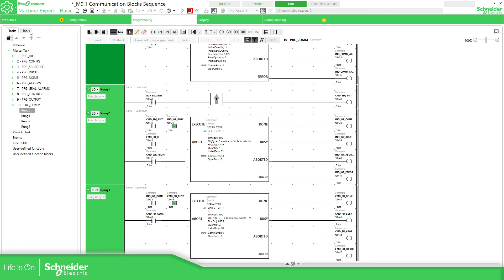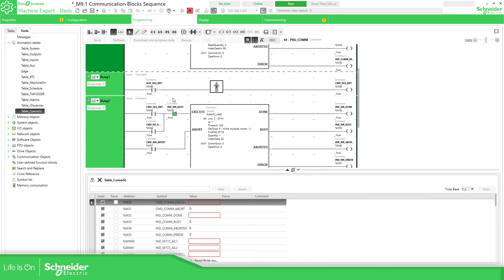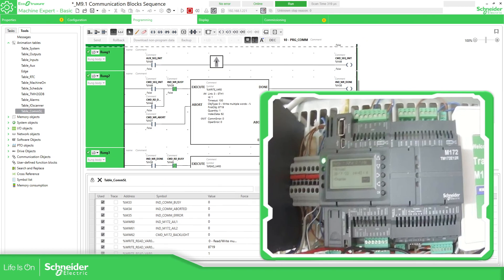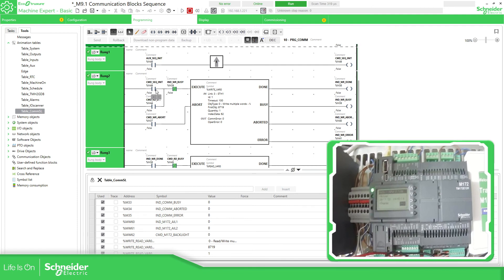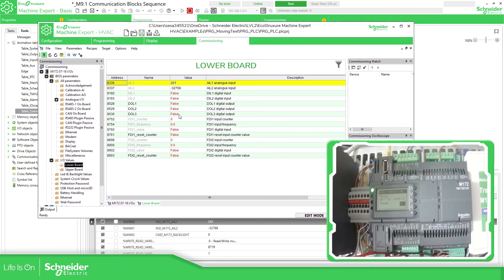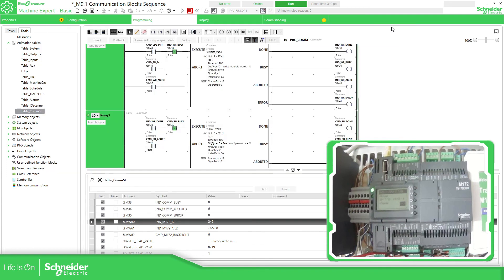I'm going to separate the write and read. Let me check the communication serial line configuration. Here I'm going to change the view — this is the PLC — and start the sequence. We can see the execution running and reading the information. This one is the temperature reading. I'll touch the probe just to show you it's going to rise. You can see it's rising, which is good. Now opening the other software, Machine Expert HVAC, already connected, and we can read the information — it matches.